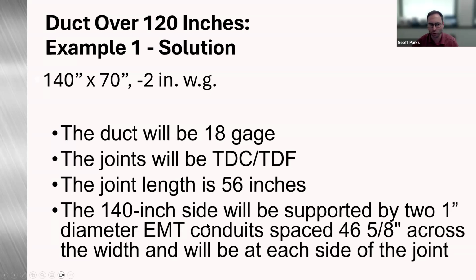What I took out of this example that was in the first go around was how to size the EMT conduit, and that would be sized per table 2-38 for negative pressure, which we're not getting into today, but that's how we came up with the 1-inch diameter.